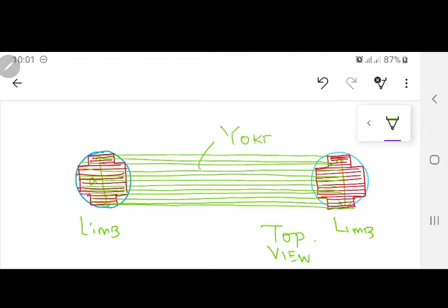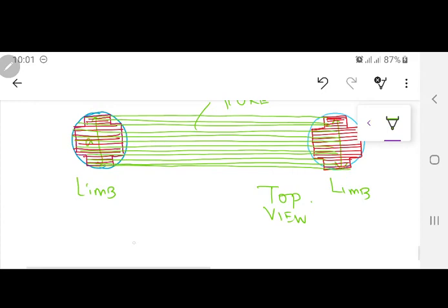Now, since this is a two-dimensional picture in front of you, the yoke over here is rectangular or square in nature. That I have still decided on this one, because this length is A. Now when I am going to decide on the yoke area AY, till now I had decided AC in the last lecture, that was the area of the core.